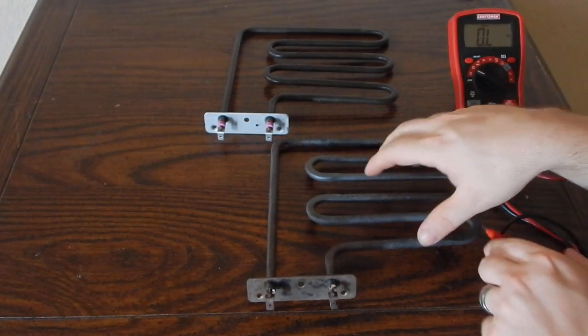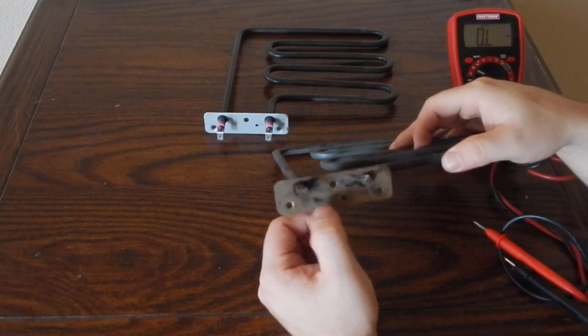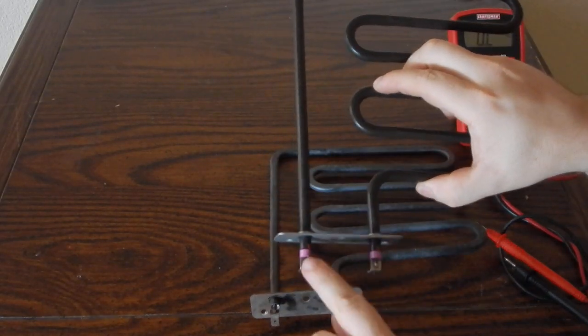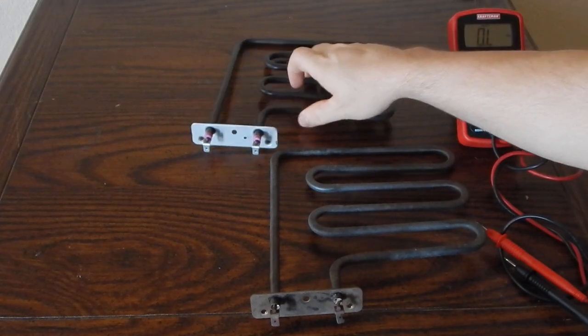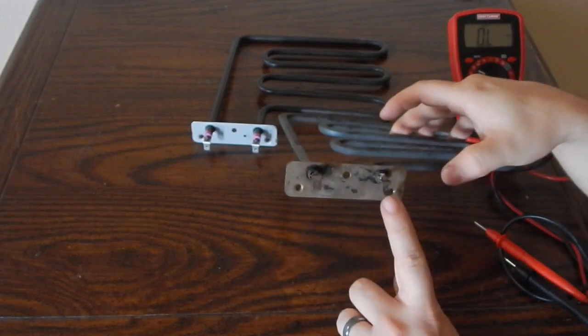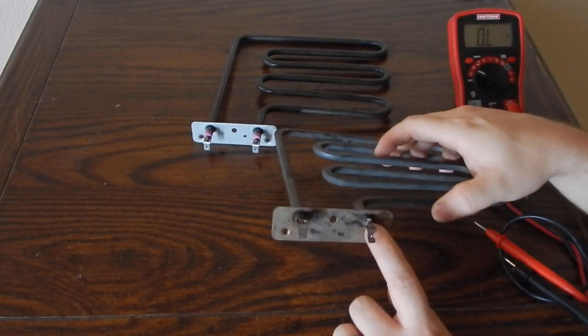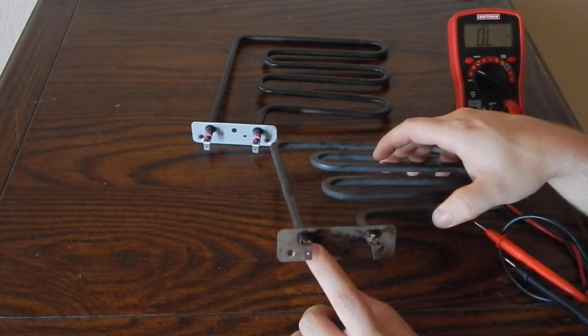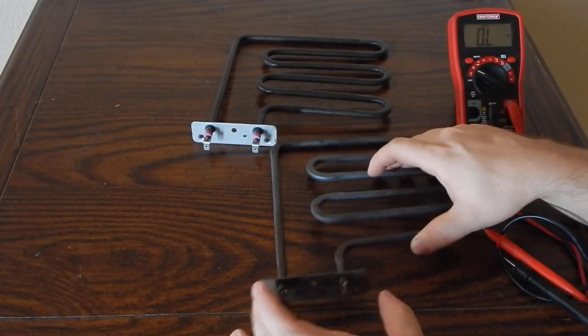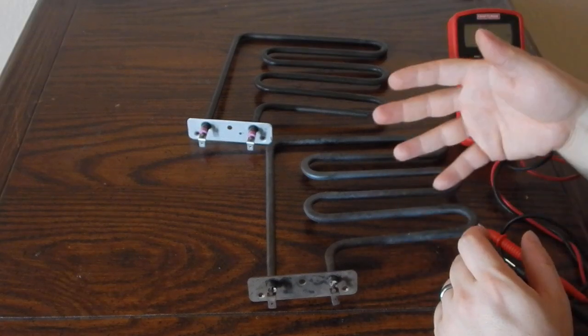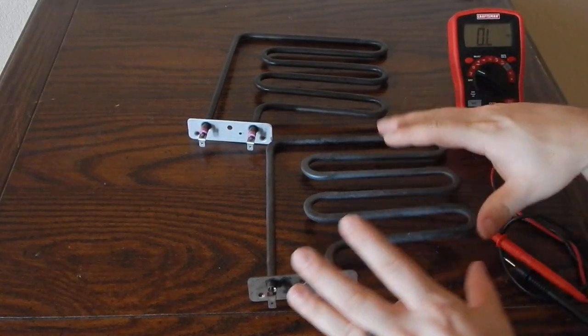Now what probably happened is, as you can see the plugs, here's a new one and you can see these plugs are right here, they're pink, you can't miss them. The plugs are missing on this one and this is probably magnesium oxide or some other ceramic powder kind of material, and they put that on the outside of the wire there and then encase that, like I said earlier, with the steel.